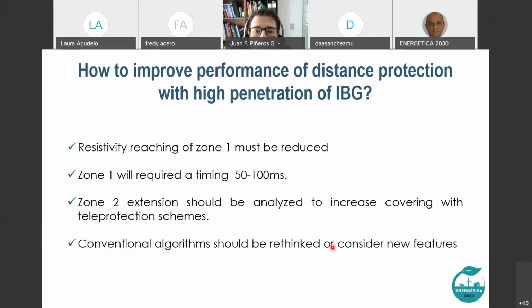How to improve then the performance of distance protection, given what we are observing in the scenario with high penetration of this generation, IBG? The first point is we will have to reduce the resistive reach of zone 1. And as you saw in the graphics I was showing you, even if you reduce it, there are some cases where you cannot solve the problem, because you cannot put a setting of only 1 or 2 ohms for the resistive reach of zone 1, because then you kill the dependability of the protection. Then, because of that, one possible solution could be that zone 1 will require timing.